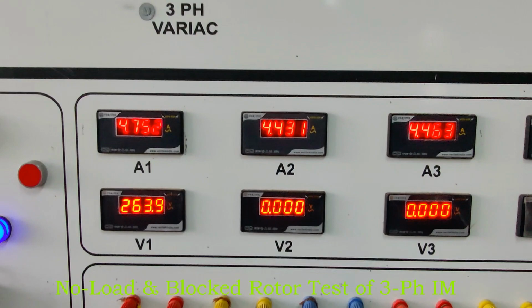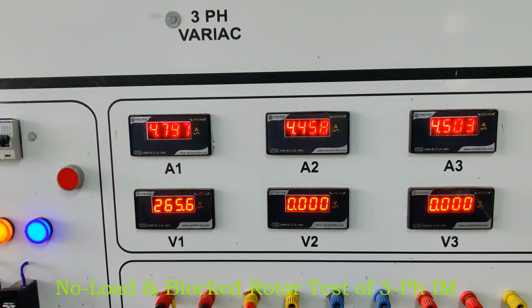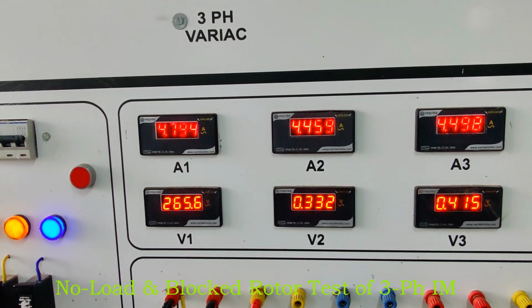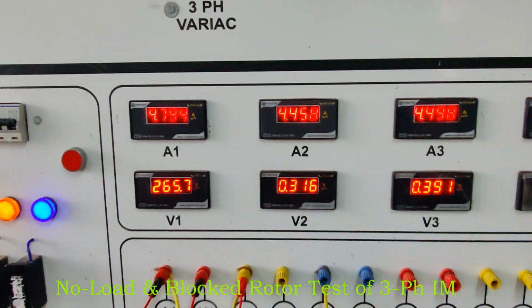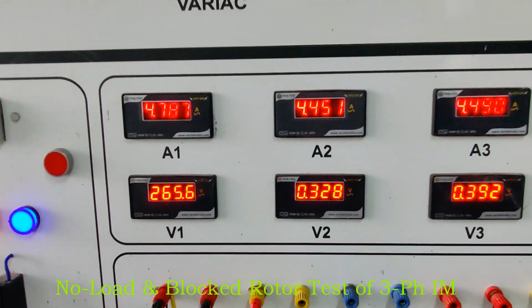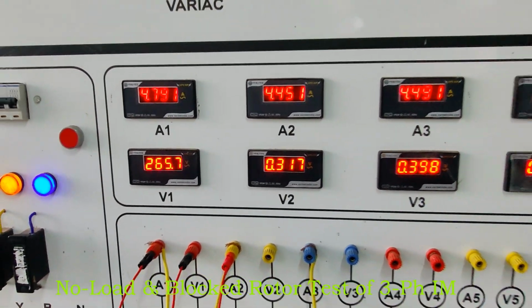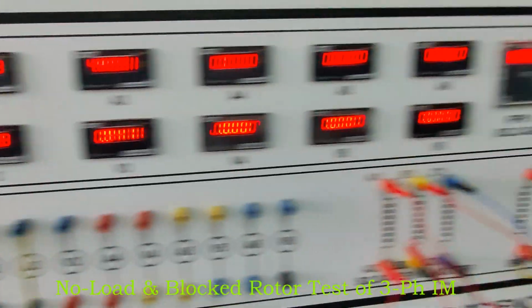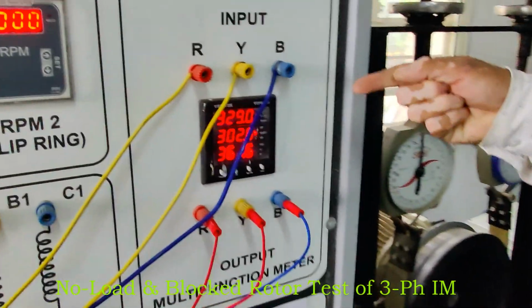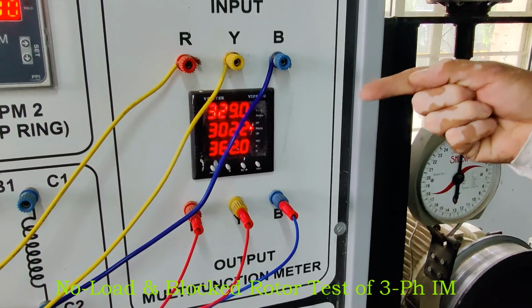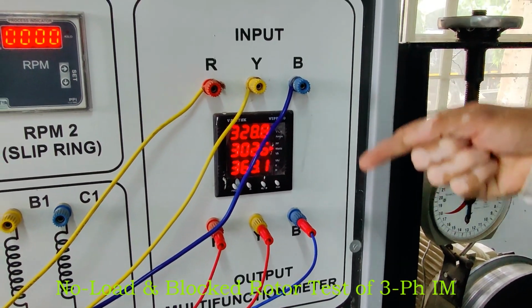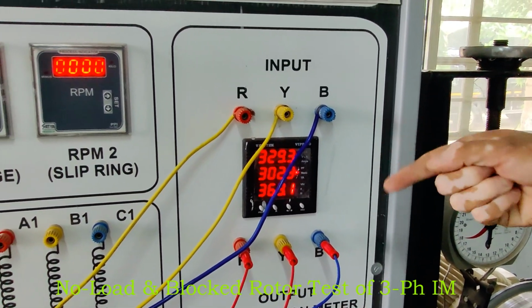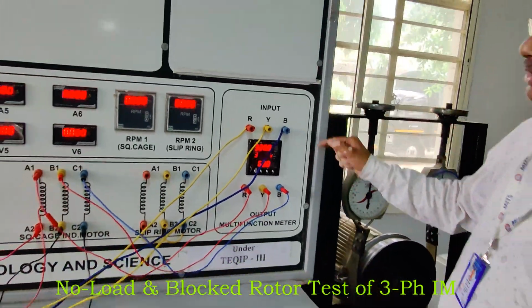Yes, this is the rated current. 4.7, it's a rated current. 4.4, 4.4, and the short circuit voltage V1, and it's a power. The power is high as compared to no load. 328, 302, 362. By adding all this power, we can calculate short circuit or block rotor test power.